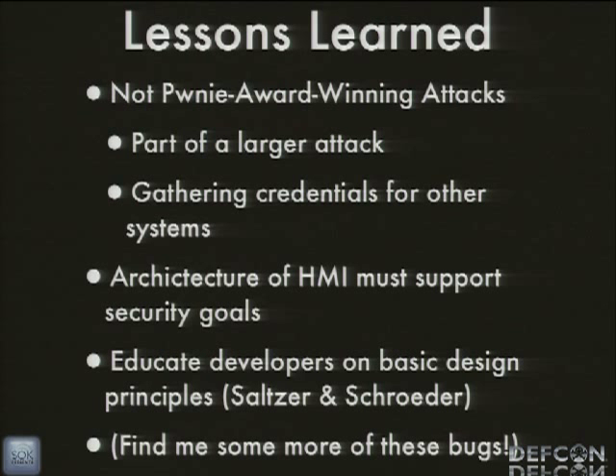These are not Pwnie-Award-Winning Attacks. They're not hard to do, and they're not even something you can just attack a system with right now — most of these require some level of access already, but you can escalate what you're allowed to be doing. It's part of a larger attack. The really helpful thing is if you're a pen tester facing systems like this, this is a great place to gather credentials for other systems — because I guarantee they're going to reuse this password somewhere else. The lesson learned for HMI development is that the architecture of your HMI must support your security goals. You can't run it as one monolithic piece of software in one user — you're going to have to break it out, run part of it as a daemon or as admin or system, break it out into client-server at least across users.